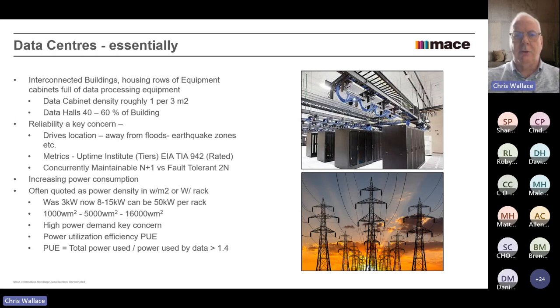At the back of that, you've got all the cooling and the switch room. I say cooling, in this part of the world, typically, we still are refrigerating or cooling the data center. Elsewhere in the world, obviously in the Nordics and some places in America, they can just blow temperate air through, and that will be sufficient to cool the building. But typically in Asia, you find that the white space won't be the whole building. It might actually be between 40 to 60% of the overall built space. You might get a little bit more than that, but probably not much more than 60%. If you get 60%, you're probably doing okay.